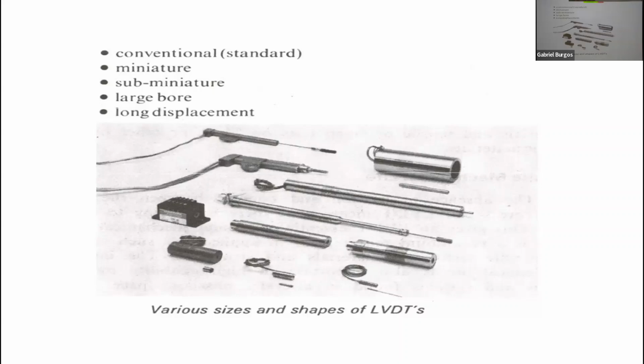Here's a unit with a very large bore, because you can put a pipe through the middle of it, as we'll see in a couple of minutes. As long as the pipe is non-magnetic, say stainless steel or some kind of Inconel or other material that's not very magnetic, the AC field of the LVDT will get through the pipe to the core inside.